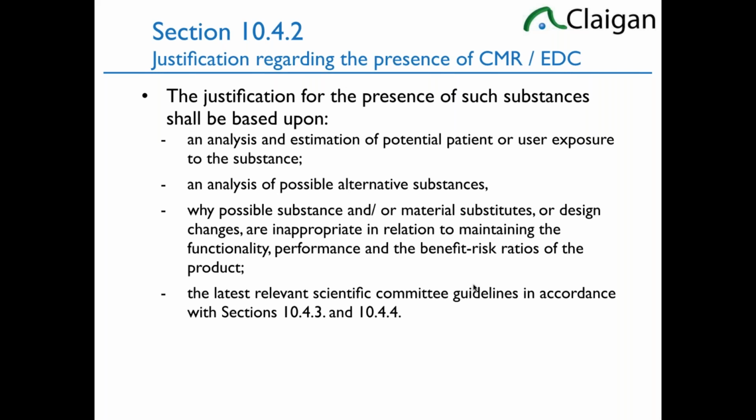Why possible substances and/or material substitutes or design changes are inappropriate in relation to maintaining the functionality, performance, and the benefit-risk ratios of the product. You can say, I can't use adipates in this as a plasticizer. Well, these people do. It becomes very difficult. So if somebody else can do it, this justification becomes far, far more difficult. It also has to take into account the latest scientific committee guidelines in accordance with section 10.4.3 and 10.4.4, which we'll discuss in the next two sections.